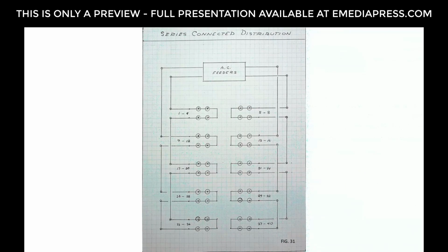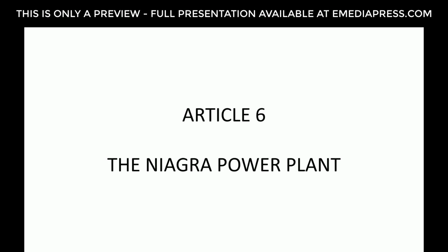In the constant current, there's no transformers because the whole thing operates at high voltage, even though in later time they did put in transformers because the voltages were so dangerous that any contact with the luminary device while it was on could be lethal. So some systems did start breaking up. Most of this started disappearing off the utility poles in 1958. You can still see little scraps of it around, but the last use of this is airport lighting systems where they hook all the incandescent lamps in series, and that may even be gone now. I will have no more text I'll read at this point. I'll just kind of talk about stuff.